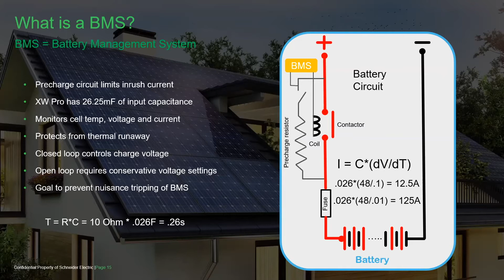When we're talking open loop, that means there's no communication between the BMS and the charger. You could use our battery monitor for state of charge control functionality with the Pro. The charging voltage is set manually per recommendation by the battery manufacturer, as well as how deeply they recommend you discharge their battery. By the way, we've been operating open loop with SimpliPhi for many years without any problems.